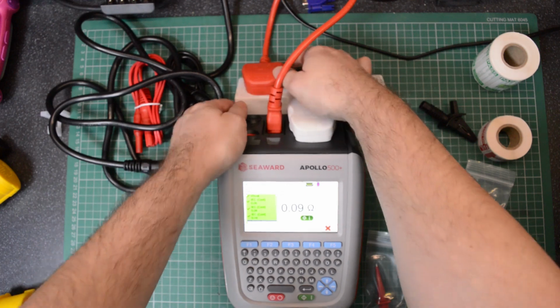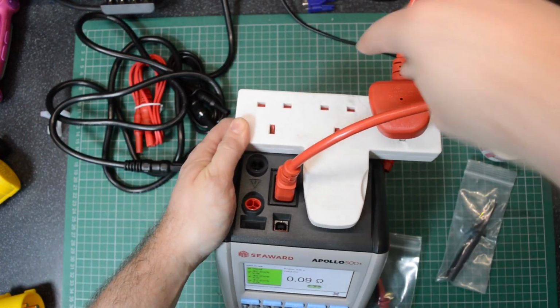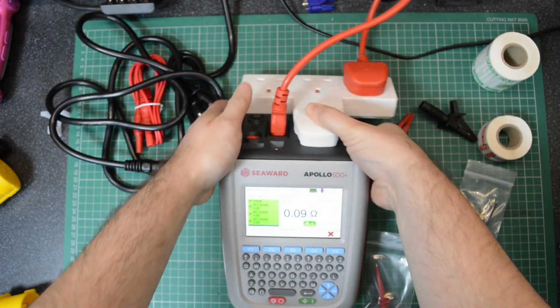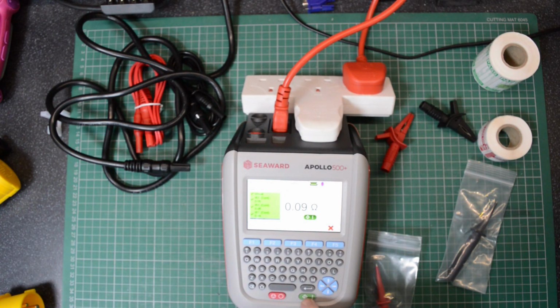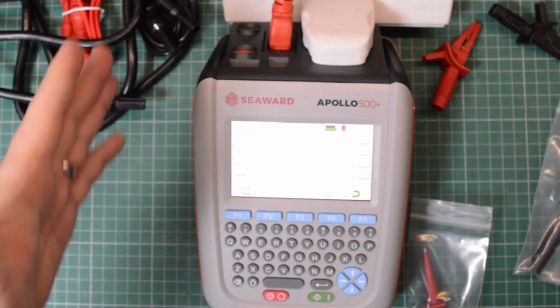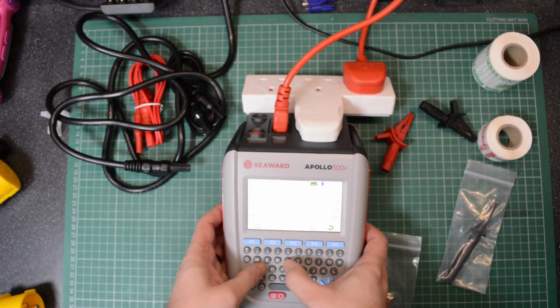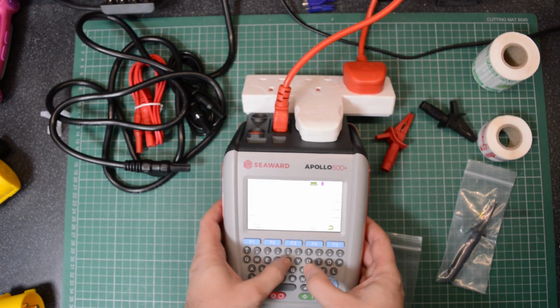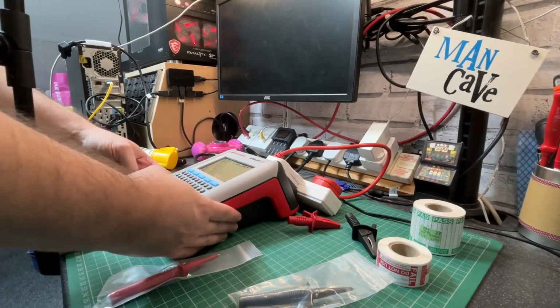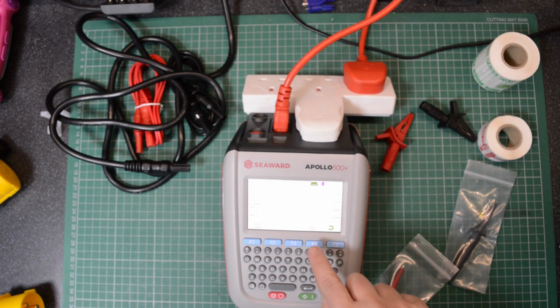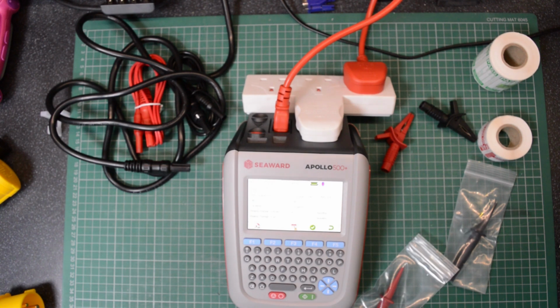So I'm just going to go ahead and put it back into the first socket. You can set these up so you can have 4, 6, 8, 3, however many ways you want. 0.09 again. And that should now move on to the insulation resistance test at 500 volts, and the polarity of the line and neutral. So the test has passed. You can give it some notes. I'm going to say test. There you go for YouTube, and we'll just say okay. And that's it, that's done.